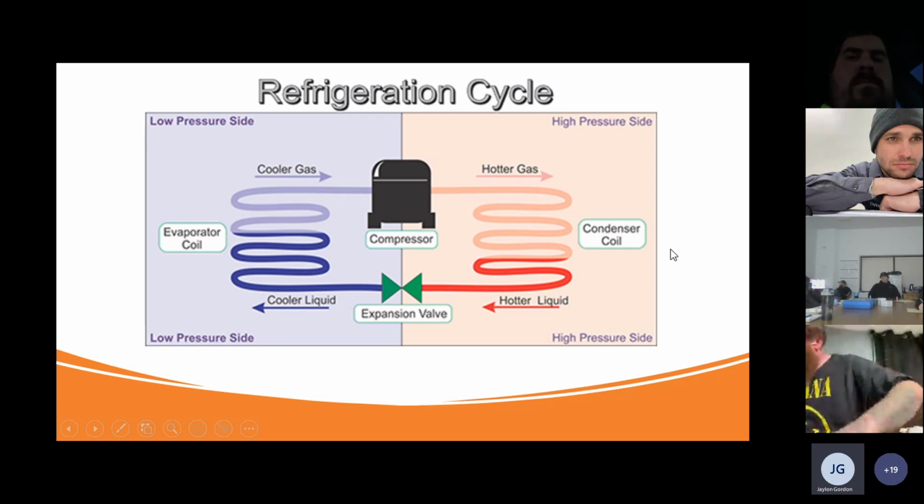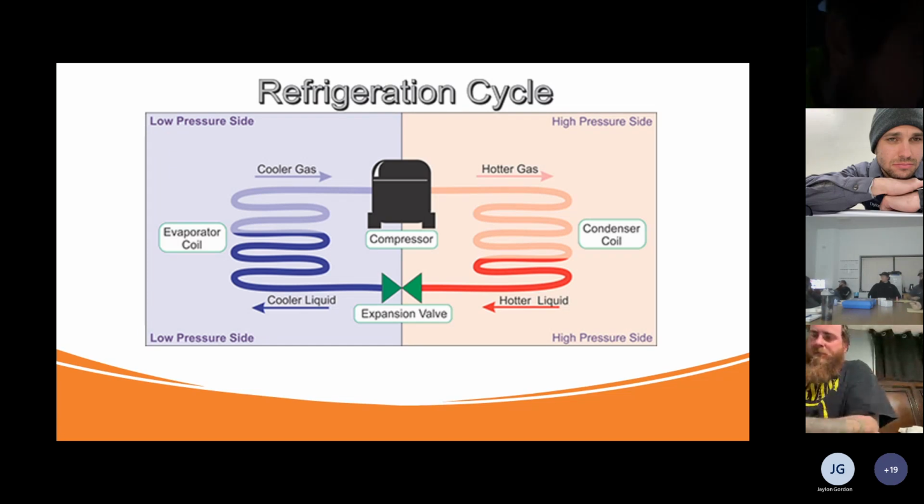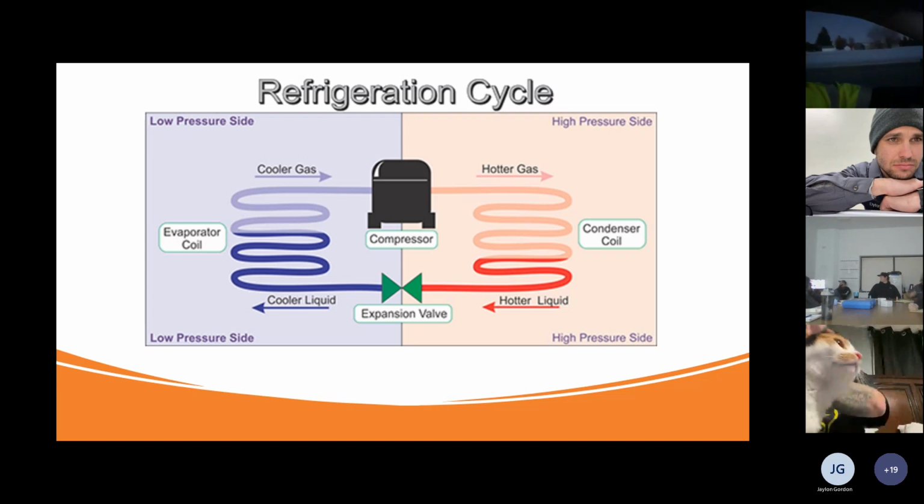No, you're good. I just wanted to ask Dustin, is it a good idea to charge liquid refrigerant into the suction line of the compressor? On this little diagram, probably not that much. What would happen if you put it... how close you are to the compressor, too. I mean, you should always charge via the liquid line, but to a certain extent you start to equalize pressures. On a rack system, you have enough pipe, distance, and volume that I've seen people do it, but in theory, you're supposed to charge via the liquid side.